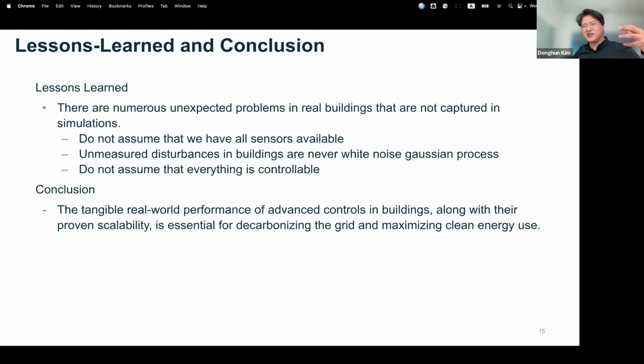That's it, and we're not able to install more, not for technical reasons, but economic reasons. A major disturbance is that buildings are never a white noise Gaussian process — that's a typical assumption in system ID or conventional stochastic MPC development, but it's not true. And do not assume everything is controllable. That's a big mistake — not because of technical reasons, we could do it, but the effort required is tremendous, so it's very difficult to change. We have to follow what it is.